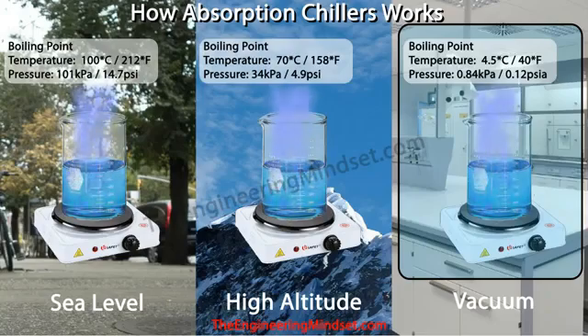So in the absorption chiller, in the evaporator and the absorber chamber, we're going to have a very, very low pressure in there, almost near vacuum. So we're going to have a low pressure of about 0.84 kPa, which is about 0.12 psia. And at that pressure, the water will boil at around 4.5 degrees Celsius or 40 degrees Fahrenheit. Now if we pass the steam over a pipe containing cold water, then the steam will transfer its thermal energy over into that pipe, and it will then condense, and the steam will then turn into a liquid water again. So throughout the absorption chiller, we're going to be boiling the water to create it into a steam, and then also be condensing it, turning it back into a liquid. And you'll see why that is in just a moment.